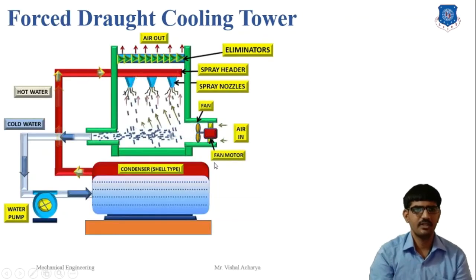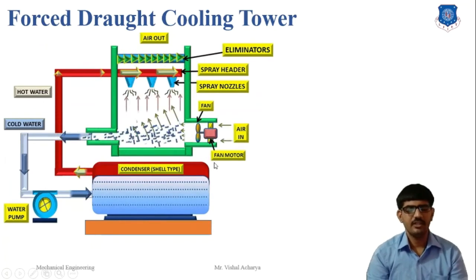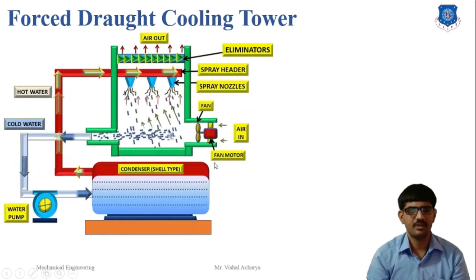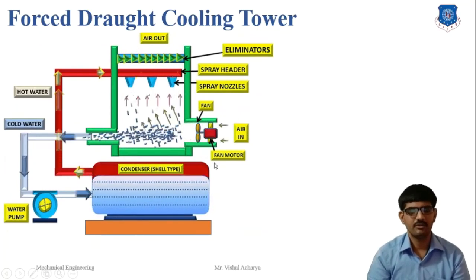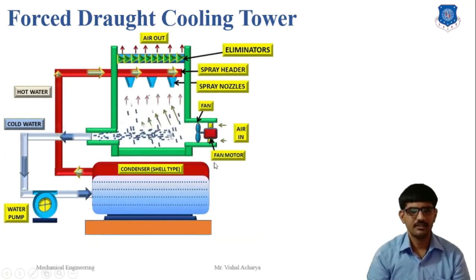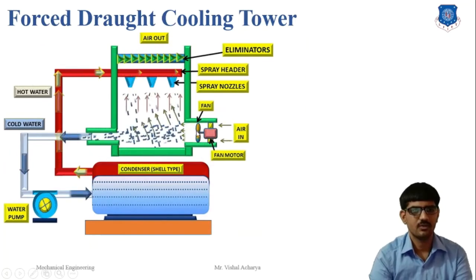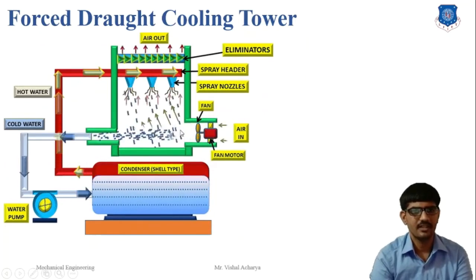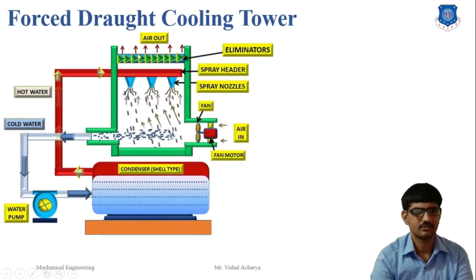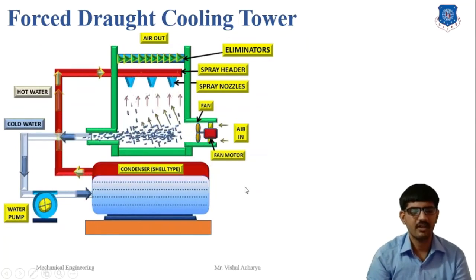The second type of cooling tower is the mechanical draft tower. In a mechanical draft cooling tower, we require mechanical components like a fan or blower for the circulation of air inside the cooling tower. The efficiency of the forced draft and induced draft cooling tower is high compared to the natural draft cooling tower. In a forced draft cooling tower, the position of the air blower is at the bottom of the cooling tower, and forced air is supplied inside the cooling tower so that the airflow moves upward.